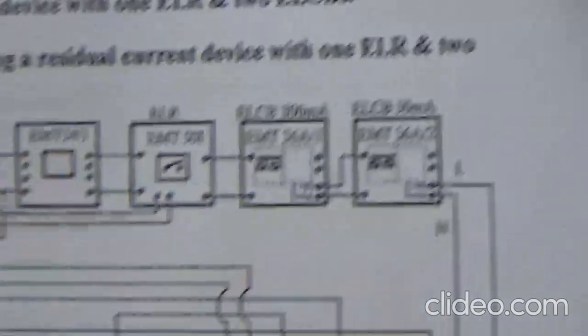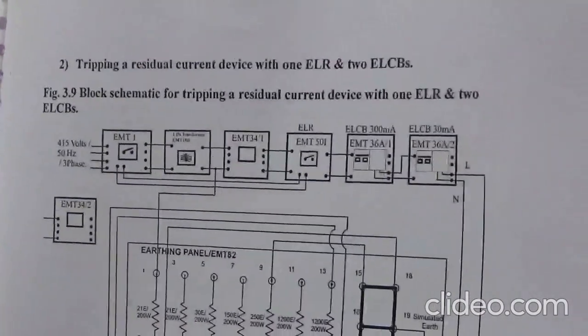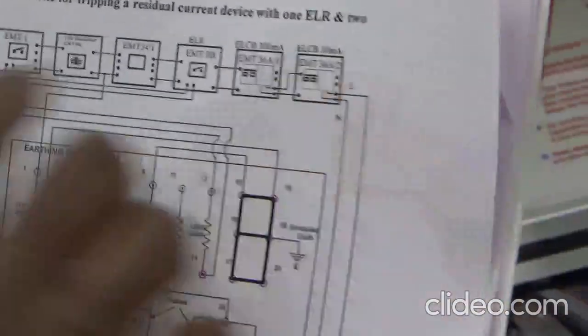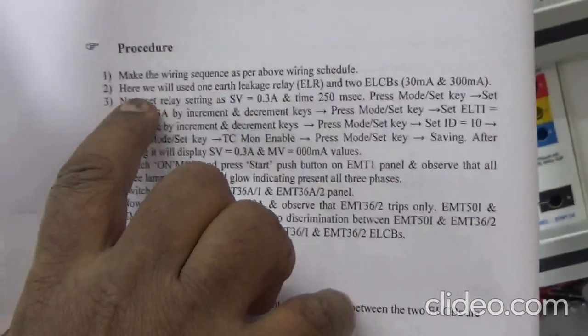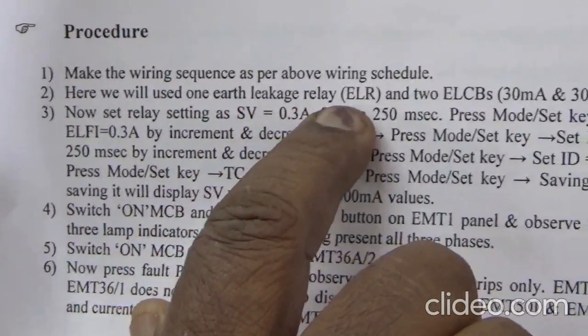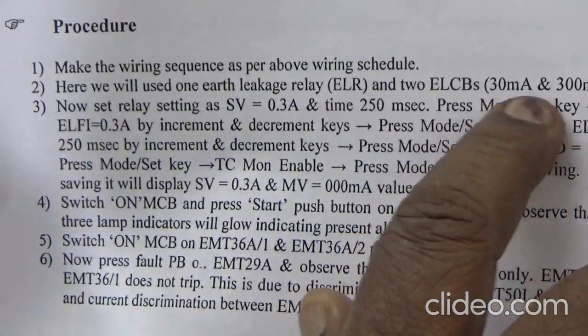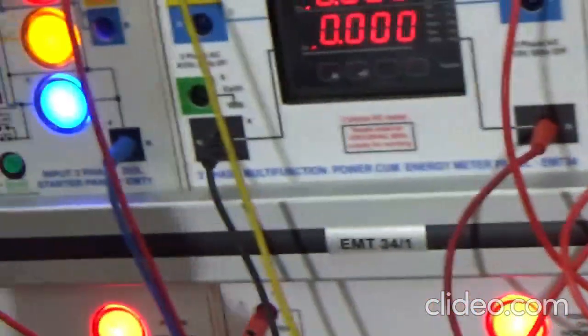Safety and earthing trainer, this is the third section. I'm going to do the second experiment, that is tripping a residual current device with one ELR and two ELCBs. With one ELR and two ELCBs. So this is the block diagram again. I have already mentioned in my second part the entire description of this, and we have got a wiring schedule. And here we have got a very beautiful way, the procedure. Make the wiring schedule. Number 2, here we will use one earth leakage relay and two ELCBs, 30 milliampere and 300 milliampere. So basically this is your 30 milliampere and the other is 300 milliampere, correct? These are two ELCBs, 1 and 2.